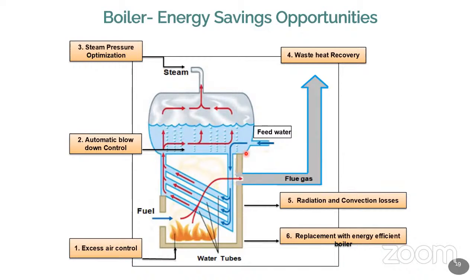What will happen if you are not doing the blow down? Scale formation will take place. When scale forms, heat transfer is blocked, so the amount of heat transferred and the amount of steam generated will be lower. That will affect the efficiency of the boiler. So regular blow down, and automatic blow down, can also be taken care of by measuring the value, right?